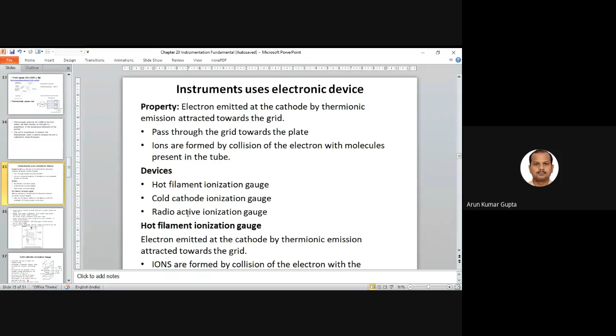These are the basic properties of electronic devices, and we have certain types of devices: the hot filament ionization gauge, the cold cathode ionization gauge, and the radioactive ionization gauge. In the hot filament ionization gauge, electrons are emitted by the cathode by thermionic emission and attracted towards the grid. Ions are formed by collision of the electrons with the gas molecules present in the tube. By measuring how many ions are formed due to the collision, we can determine the pressure.